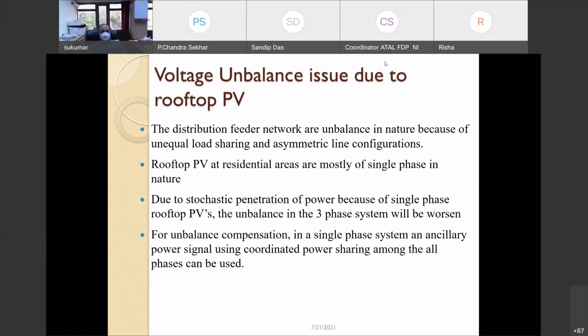Another problem is the voltage unbalance that may come because of the rooftop photovoltaic system. And this voltage unbalance becomes more prominent specifically for single phase systems, because the phase injection can be different for different installations of photovoltaic systems. Because they can be different, the current can be different and the drop in the line can be different, which can make an unbalanced scenario in the voltage. This unbalanced scenario created in the voltage due to photovoltaic injection will jeopardize the induction motor because of the negative sequence component of the voltage, and torque fluctuations of the induction motor may come into the picture.